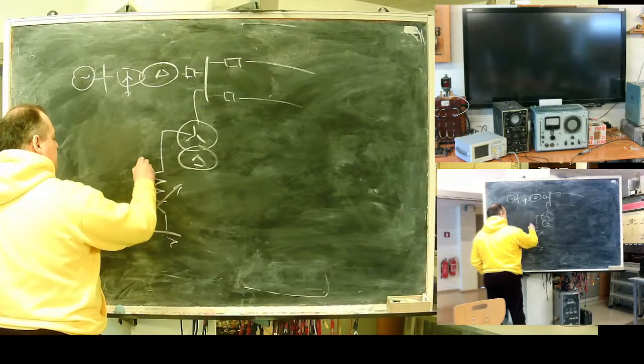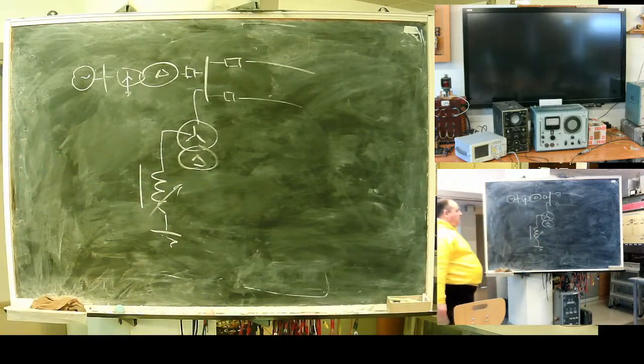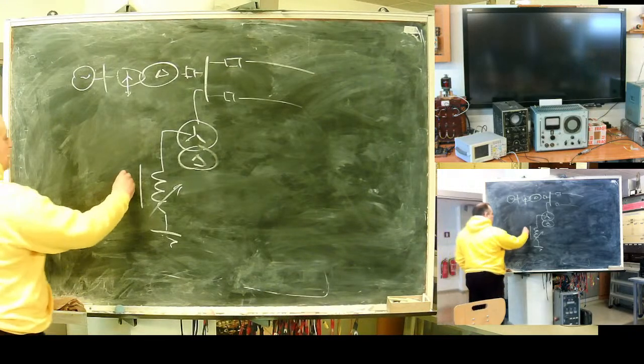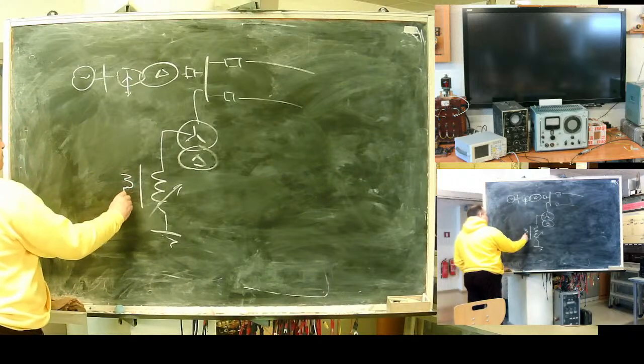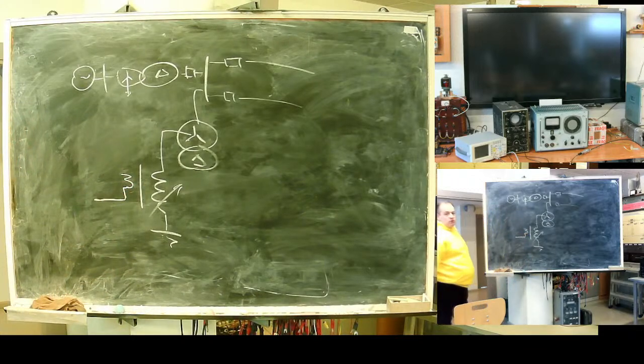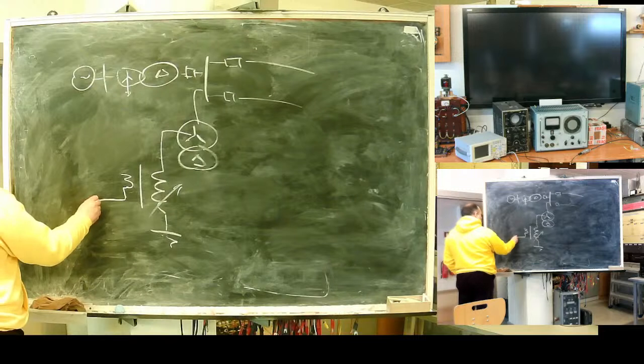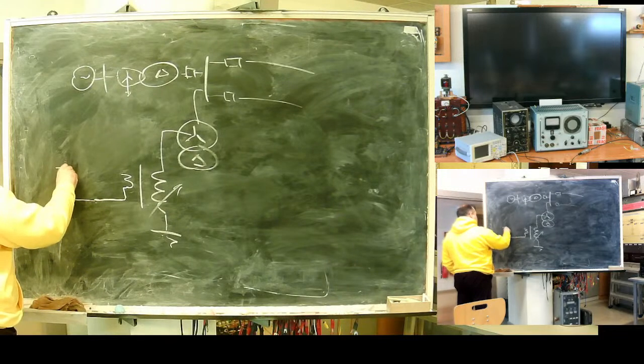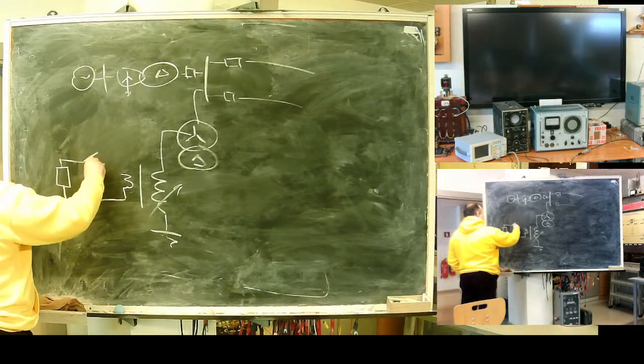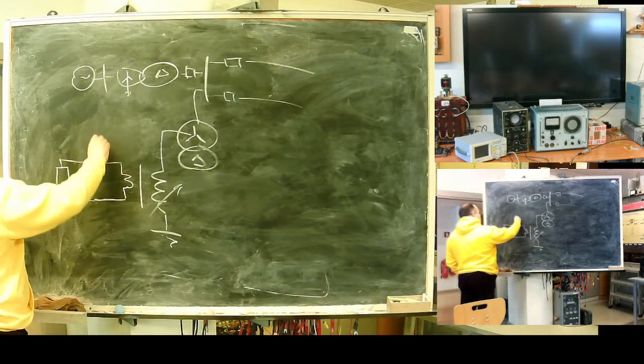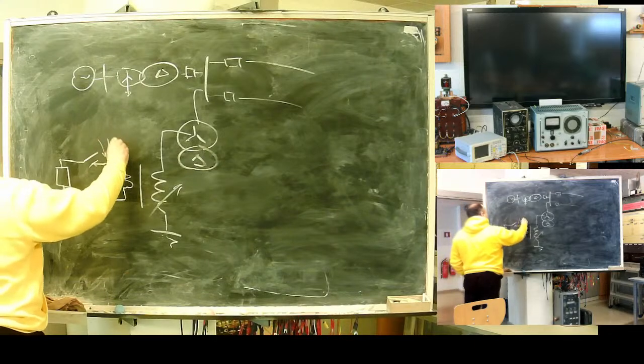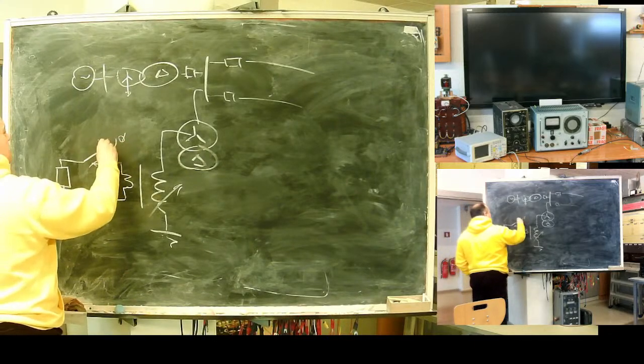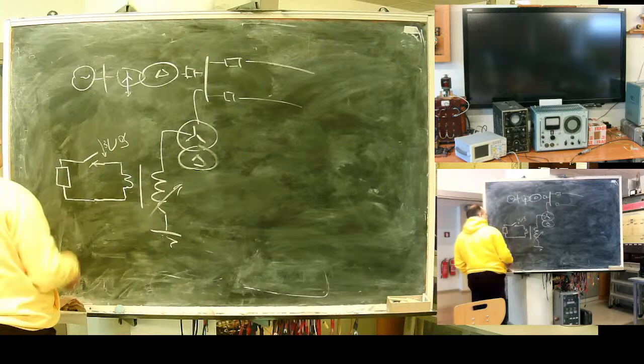And the idea was to equip the Petersen coil with a secondary winding. The secondary winding, very typical voltage 500 volts, is loaded with an active resistor. This thing closes if the zero sequence voltage is greater.